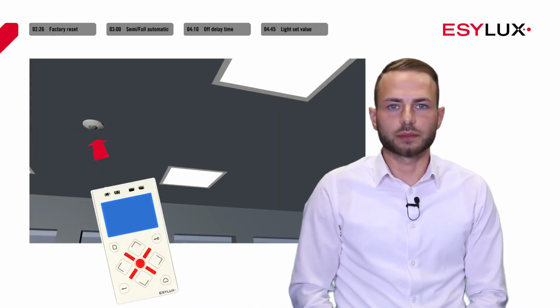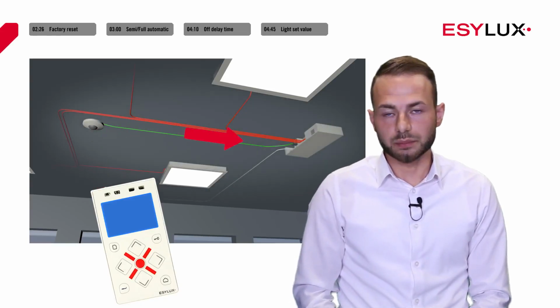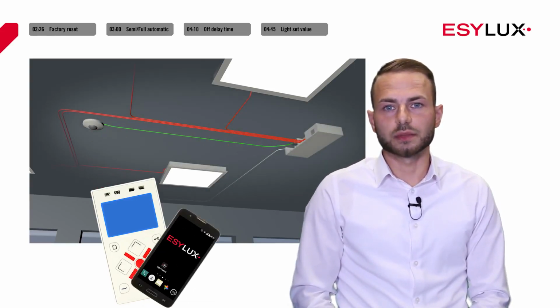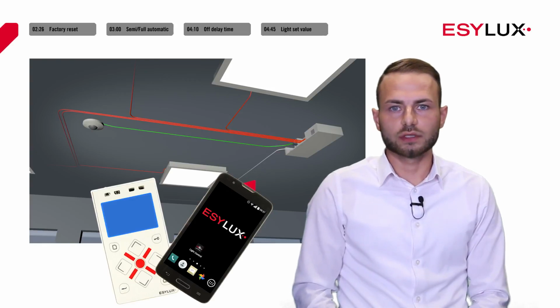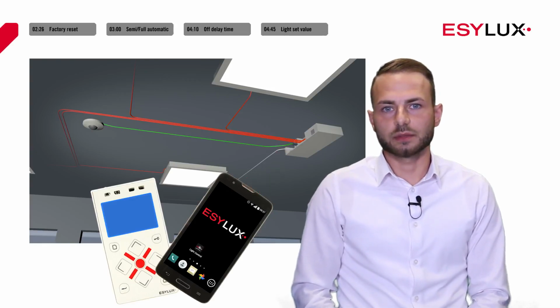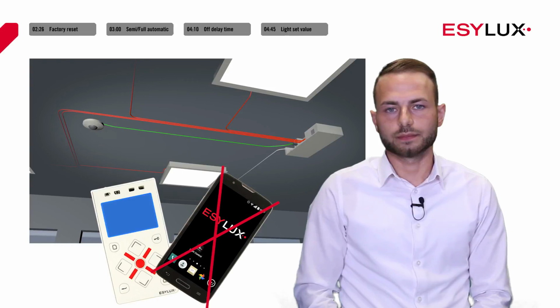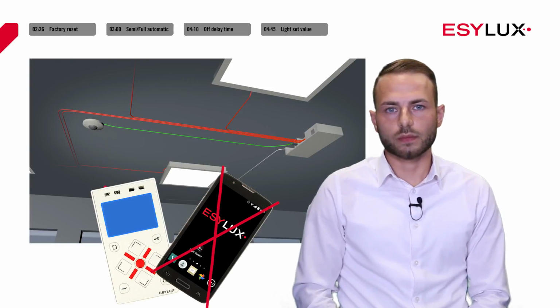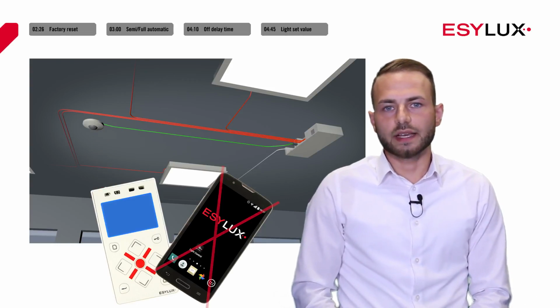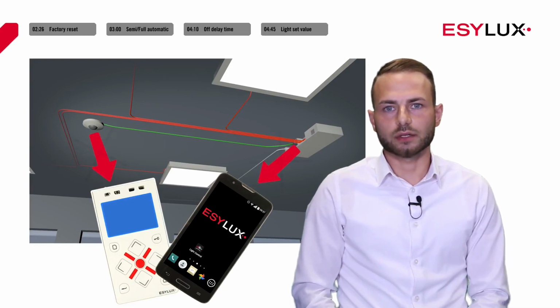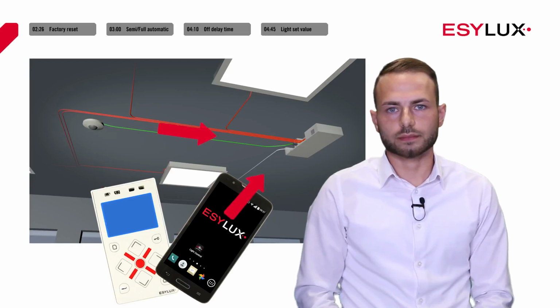The remote control sends the signal via the presence detector to the ELC. The same settings can be configured using the remote control as with the app. The remote control can also be used to configure the presence detector itself. Please note that the app and the remote control do not read out any parameters, but merely send commands and values.